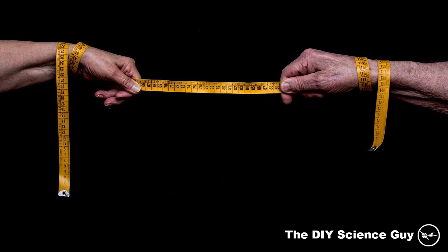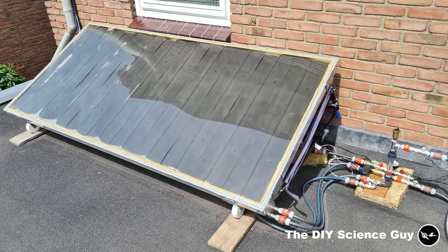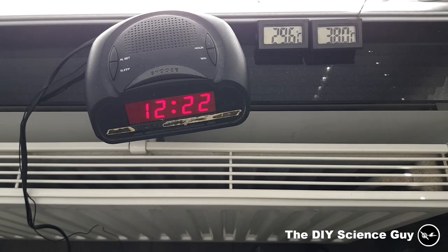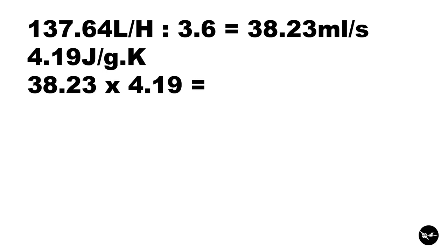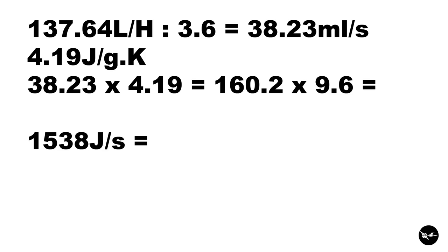I made a time lapse of the thermometers and the clock, and finally on the 27th of June at 1:35 pm, the temperature difference was 9.6 degrees. With a flow rate of 137.64 L/hr — which is 38.23 mL/s — times 4.19 J/g·K equals 160.2 J/s, times the temperature difference of 9.6°C gives 1538 joules per second, or 1538 watts. So the peak performance is around 1500 watts, which is pretty close to the estimated 1600 watts.